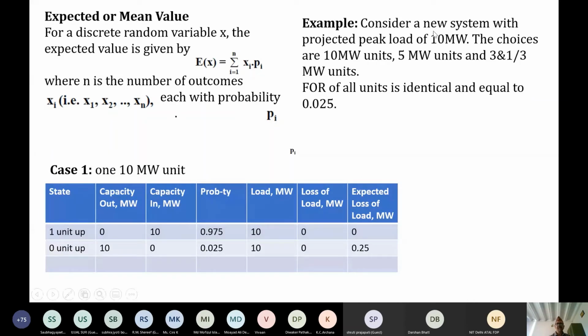Now, consider a system with a projected peak load of 10 megawatt. The choices are 10 megawatt units, 5 megawatt units, and 3 and 1/3 megawatt units. The forced outage rate of all units is identical and equal to 0.025. So we have a 10 megawatt peak load system, and the choices for us to design the system are: I have a 10 megawatt unit, I have a 5 megawatt unit, and I have 3.333 megawatt units. The forced outage rate for all these units is equal, 0.025.